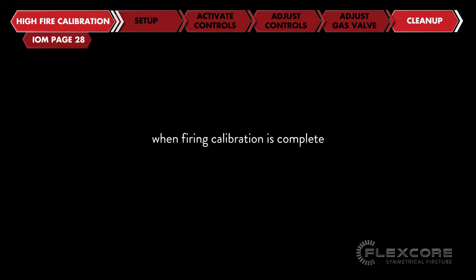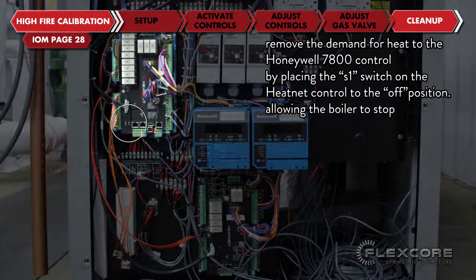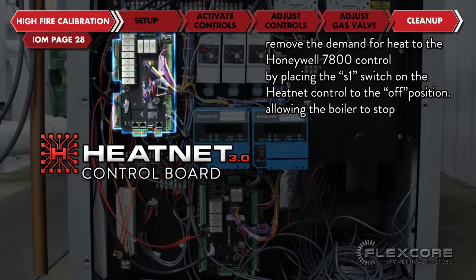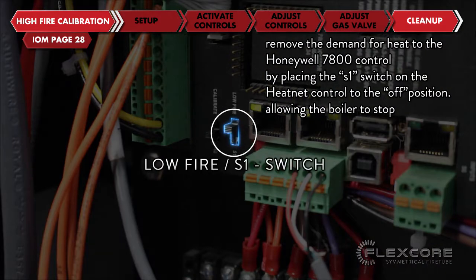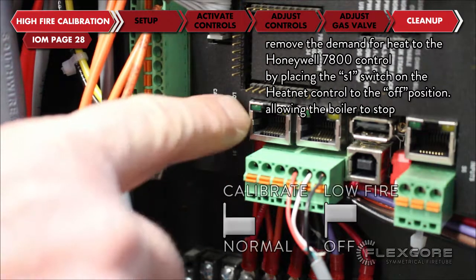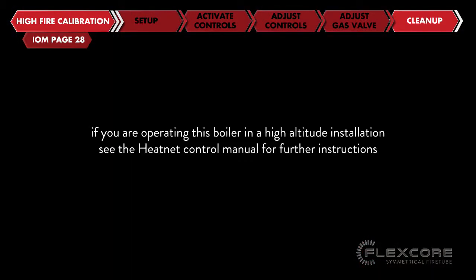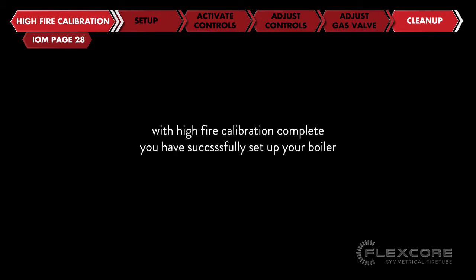When the firing calibration is complete, remove the demand for heat to the Honeywell 7800 control by placing the S1 switch on the heat net control to the off position, allowing the boiler to stop. If you are operating this boiler in a high altitude installation, see the heat net control manual for further instructions. With high fire calibration complete, you have successfully set up your boiler.